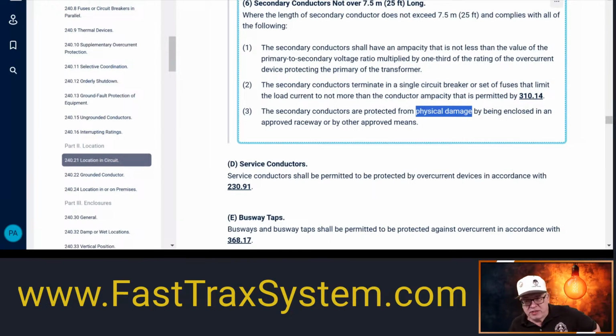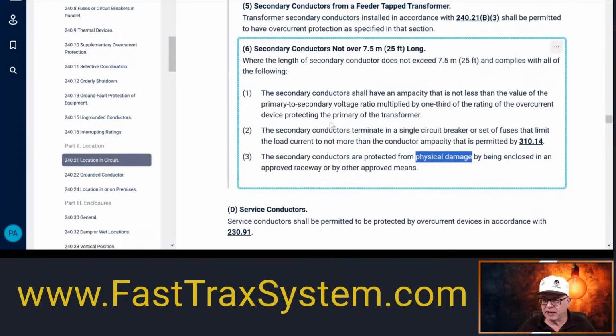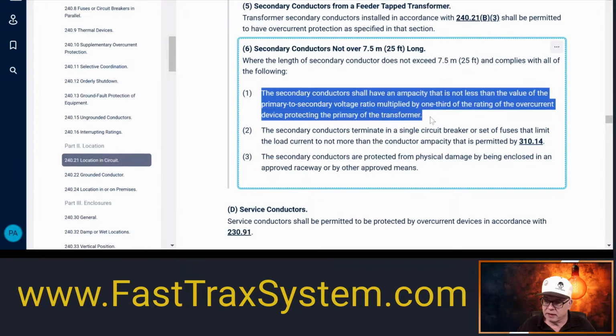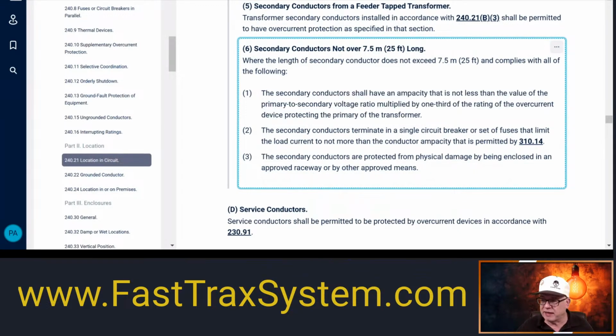All right, it's pretty simple, pretty straightforward when it comes to those secondary conductors, okay? But again, remembering this is a minimum, and depending on the load, we said this was a 75 kVA transformer. So I'm going to get 200 amps out of that. That 96 amps minimum size conductor isn't going to do anything for me. So I'm going to end up increasing my conductor in order to be able to terminate it into whatever device I'm terminating to. And I need to make sure that that conductor is protected at its ampacity, right? Okay, so they kind of work together, if you will.